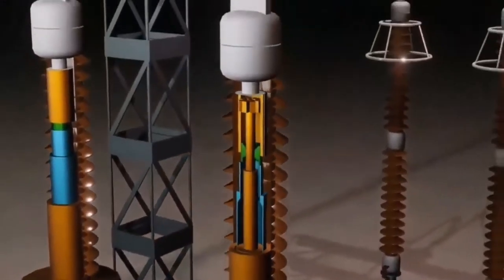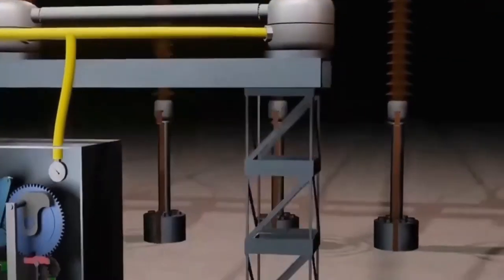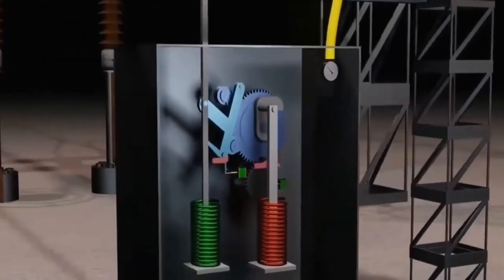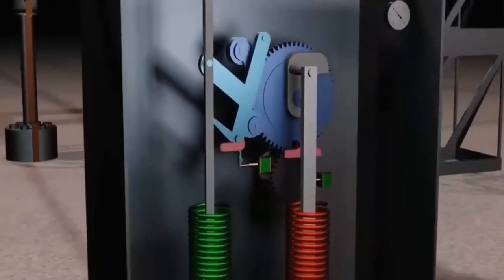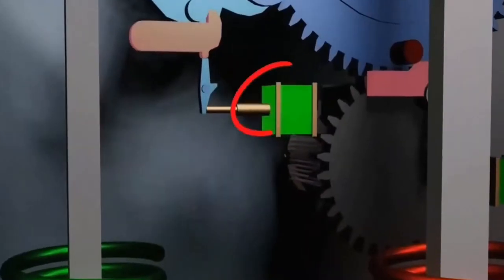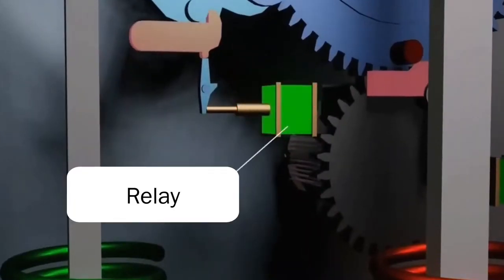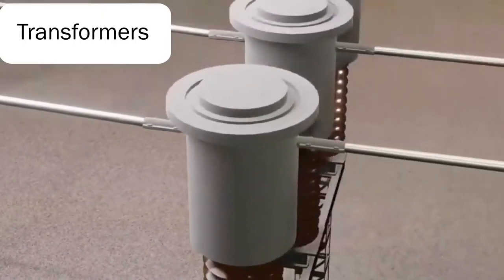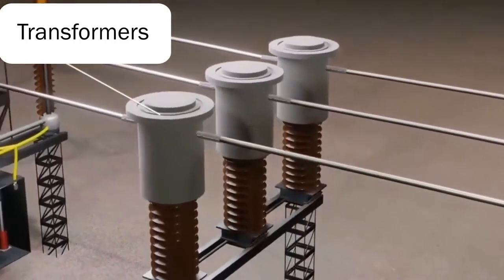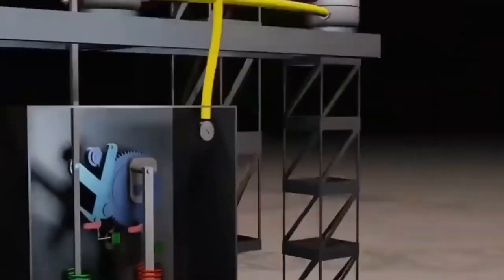This is where the mechanical controller at the bottom comes into play. The controller has two springs underneath, already in a compressed state. There is a plunger system here, connected to a relay and firmly pressing against the latch. Near the circuit breaker, there are also some current transformers. When there is a problem in the circuit, the current in the transformers increases, and they send the abnormal situation to the relay. This is when the plunger of the relay extends outward, releasing the latch.